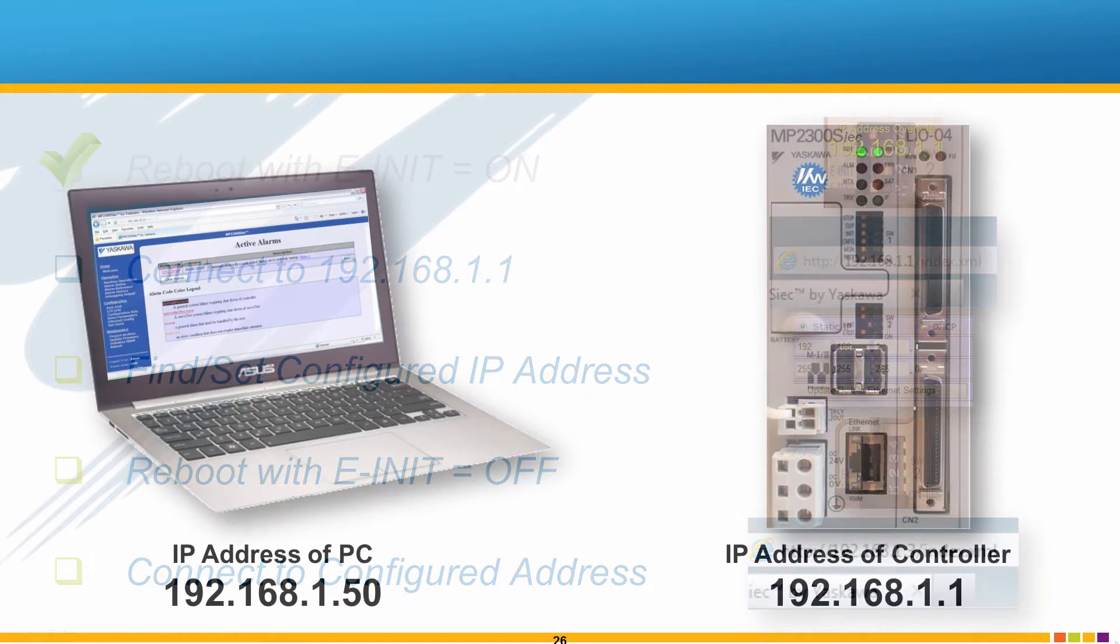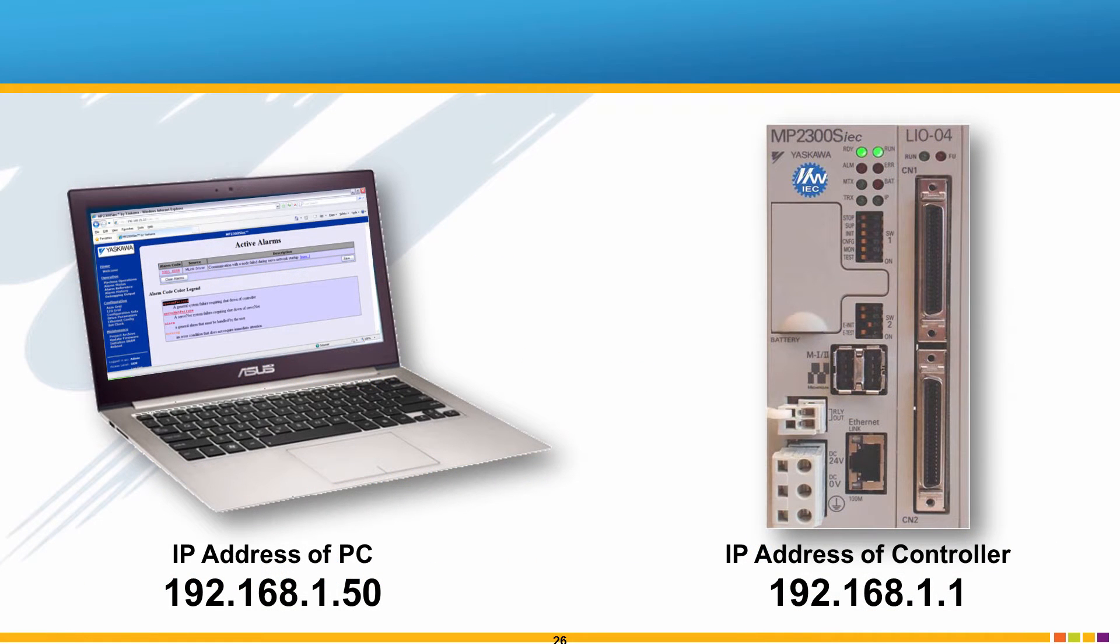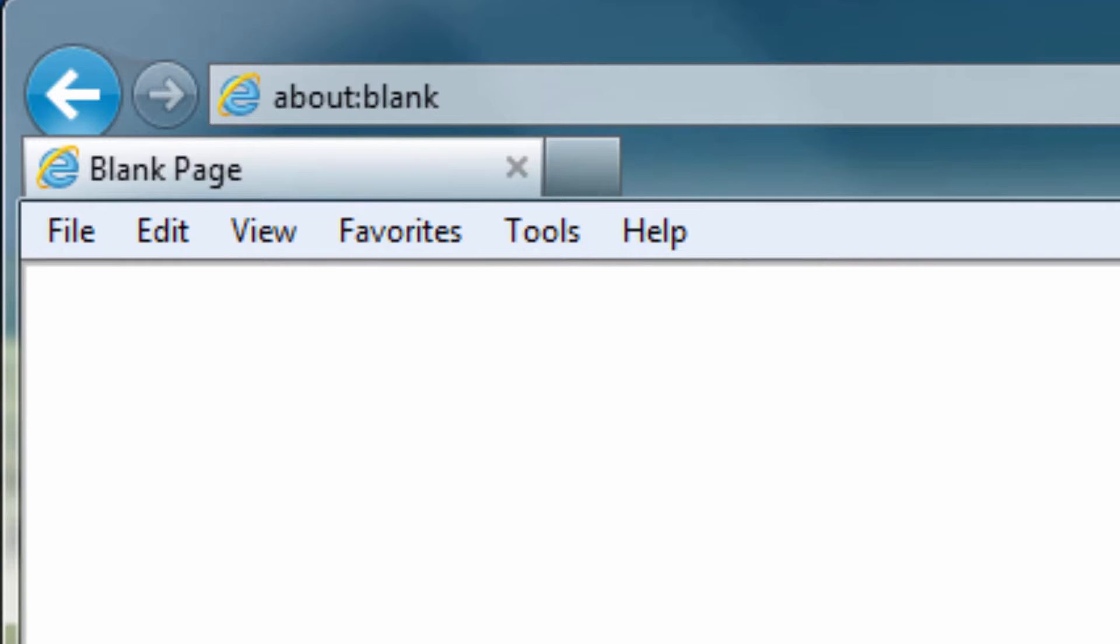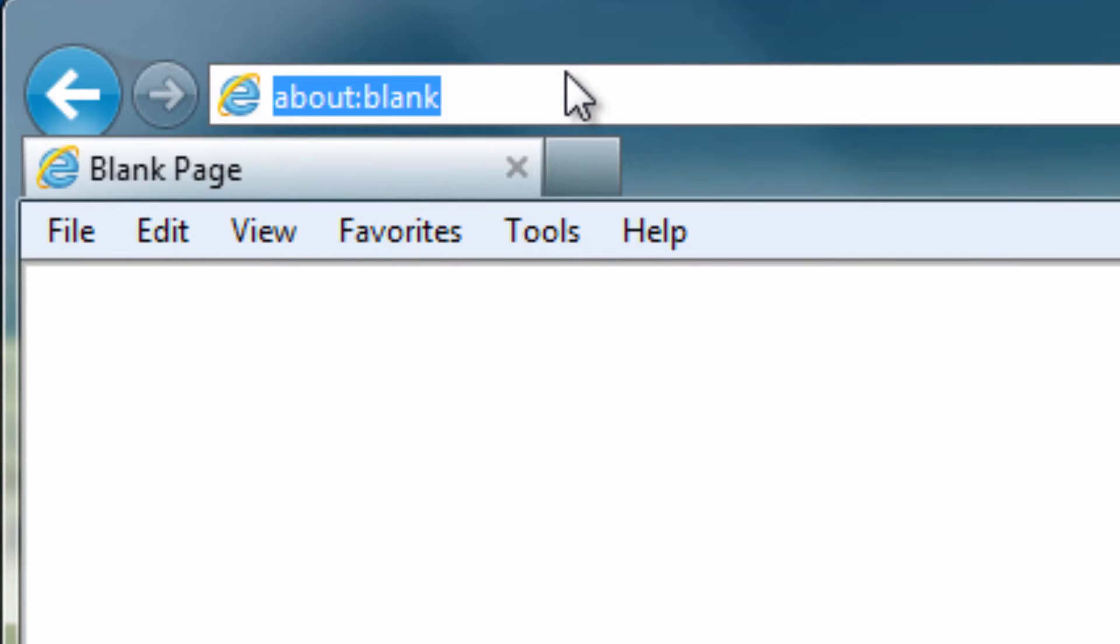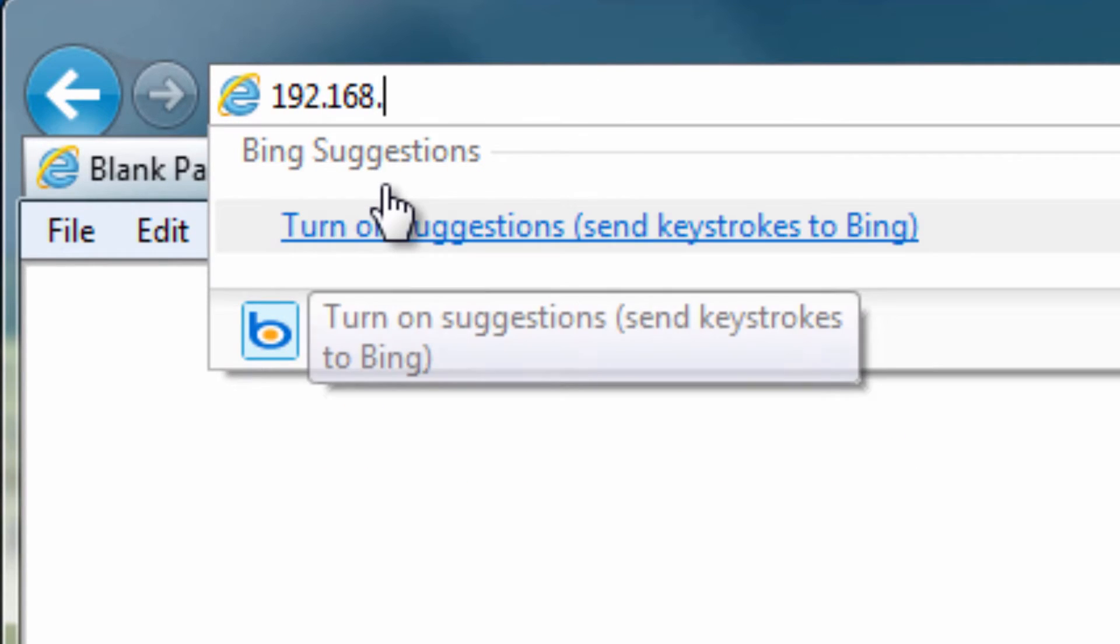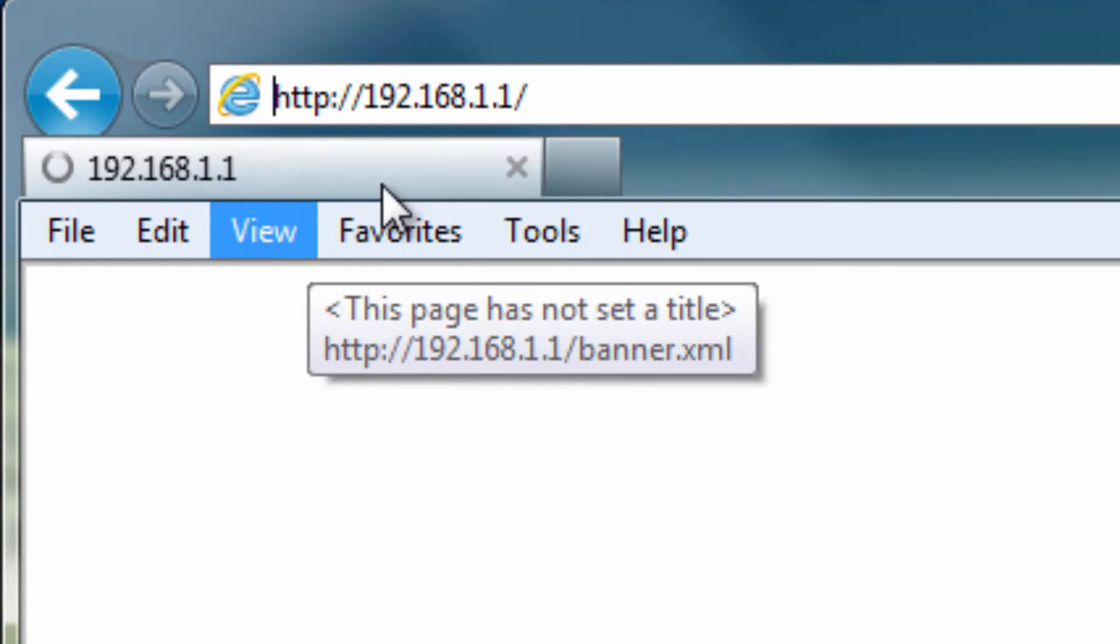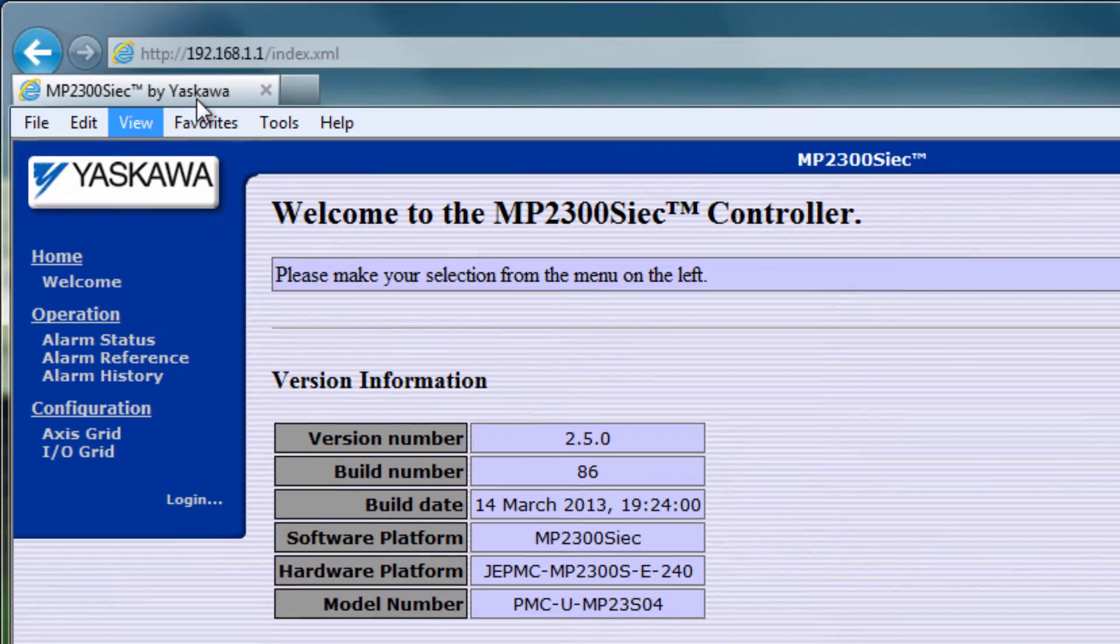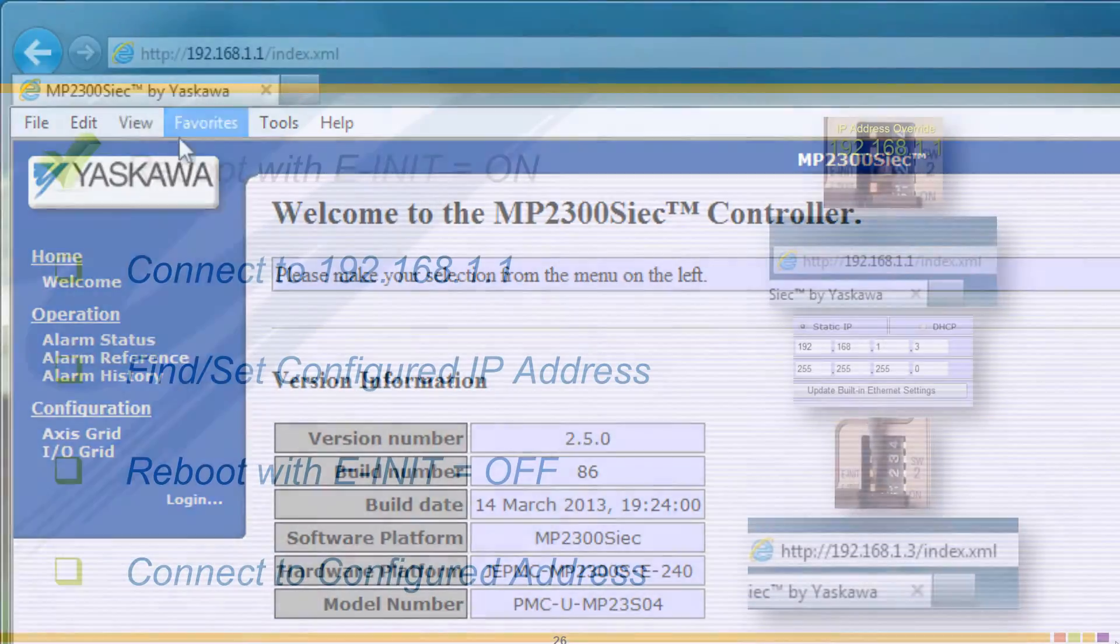If possible, simplify the Ethernet connection at this point by disconnecting the controller from any network and connect directly to the PC using a crossover cable. Then in Internet Explorer, type the controller's IP address of 192.168.1.1 and hit Enter. Success! We're now looking at the controller's built-in web page.